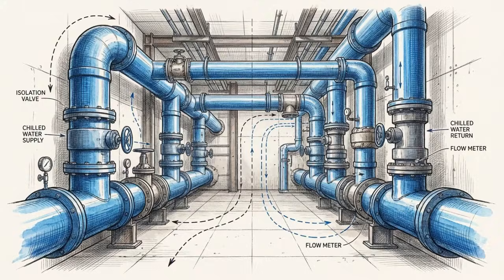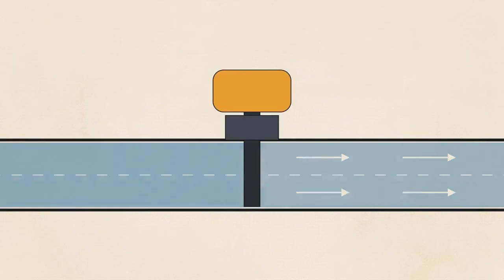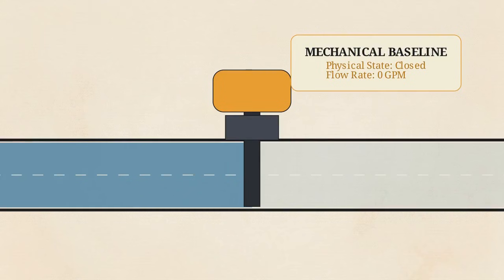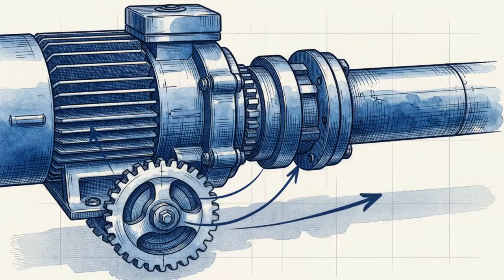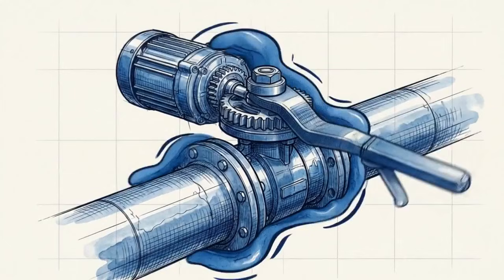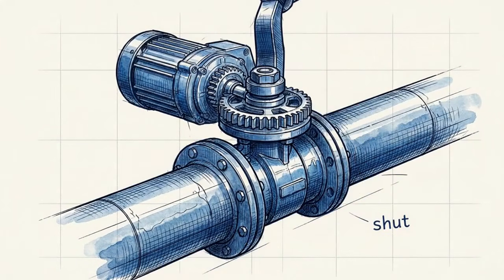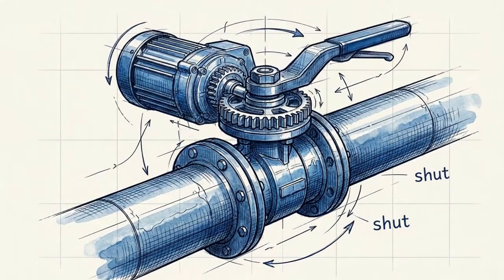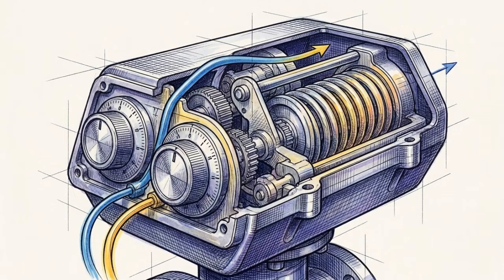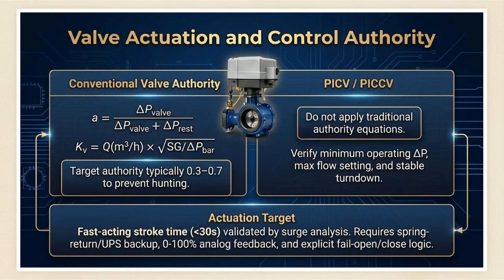To see how this architecture is built, we start at Layer 1, the physical pipe. Here, control valve actuation sets the mechanical baseline. Motorized valves must stroke in under 30 seconds to strictly prevent hydraulic shock in these complex chilled water plants. This requires battery or capacitor spring returns and 0 to 100% dual potentiometer feedback to guarantee the valve's exact physical position. This graphic details valve actuation targets.